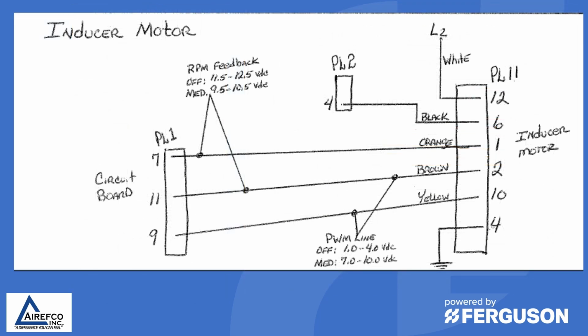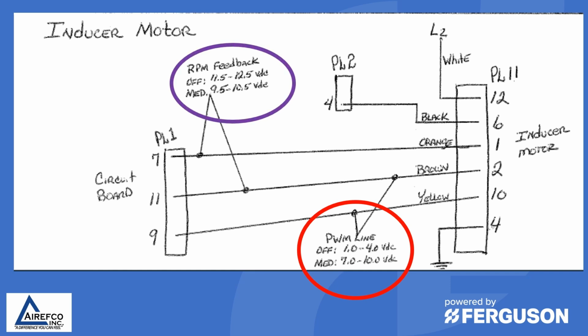Some of your inducer ECM motors also have a feedback line. In this particular example, you have a pulse width modulation line, which sends the signal from the control board to the inducer motor to run at a particular speed. And then you have wires that send a signal back to the control board, which are RPM feedback lines that tell the board that the motor is at the speed that it was commanded to. So in order to properly troubleshoot these furnace motors, you would need to have the manufacturer's troubleshooting guide that would give you these voltages that you should see for the proper operation of the inducer motor.